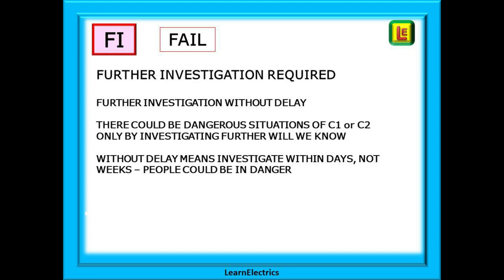FI is also a fail. FI stands for further investigation required — further investigation without delay. There could be a dangerous situation of C1 or C2, and only by investigating further will we know. Without delay means investigate within days, not weeks — people could be in danger.